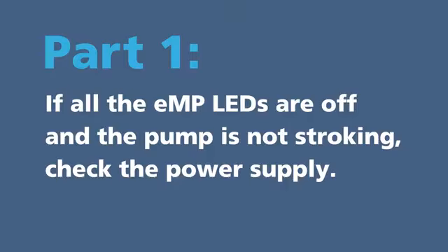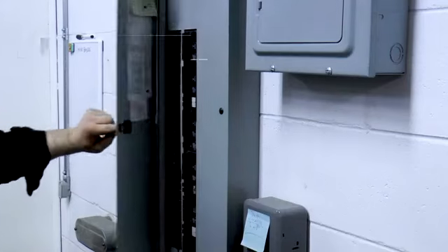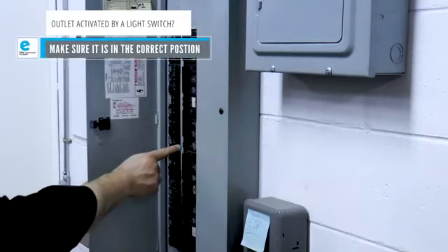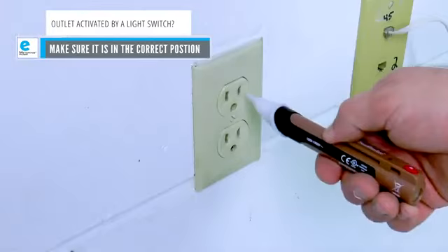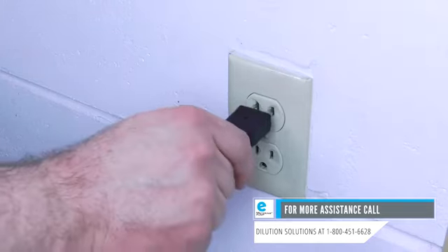Part 1. If all the eMP LEDs are off and the pump is not stroking, check the power supply. First, check if the breaker is off. If the breaker is on, the outlet could be bad. Test it with a voltage tester. If the outlet is good, plug the eMP into another outlet to confirm it works.